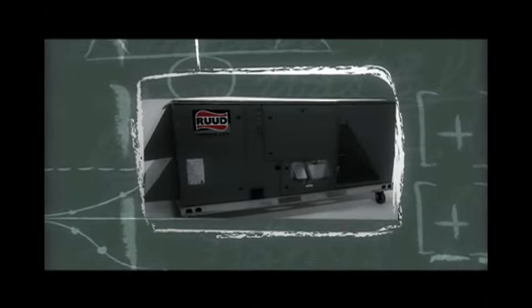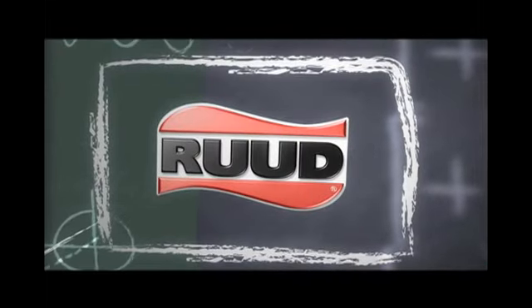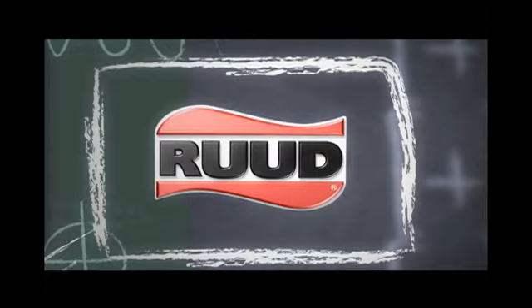The economizer, which provides free cooling when outdoor conditions are suitable and also provides fresh air to meet local code requirements, comes standard with single enthalpy controls. The controls can be upgraded to dual enthalpy easily in the field. The direct drive actuator, combined with gear drive dampers, has eliminated the need for linkage adjustment in the field. The economizer control has a minimum position set point, an outdoor air set point, a mix air set point, and a CO2 set point.